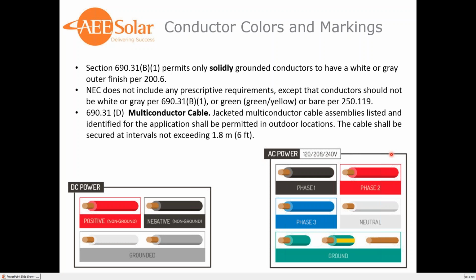690.31D, multi-conductor cable. Jacketed multi-conductor cable assemblies listed and identified for the application shall be permitted in outdoor locations. The cable shall be secured at intervals not exceeding 1.8 meters. I believe they added this because a lot of rapid shutdown devices use multi-conductor cable. For instance, SMA requires a 5-conductor cable between their initiation device and their rapid shutdown box. So I believe they just added provisions since seeing more multi-conductor cables used for rapid shutdown initiation devices.